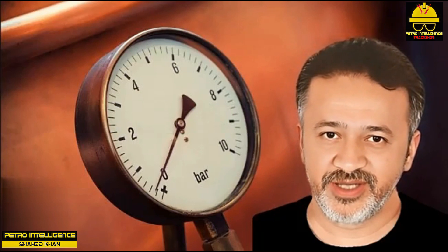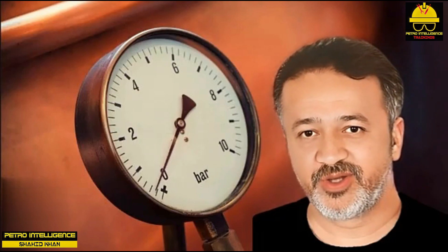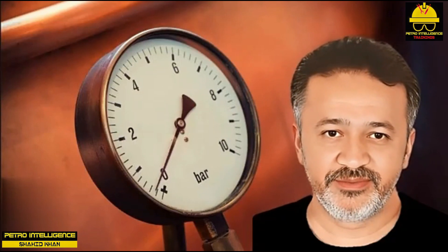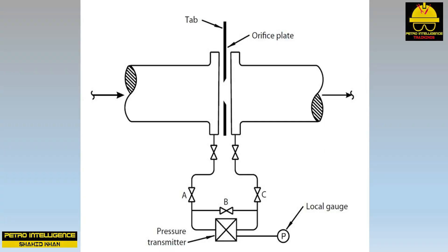Checking flows in the field: a competent engineer does not assume the flow indication shown on the control panel is correct. Referring to the picture, place an easy-to-read pressure gauge in the position shown — a digital gauge works well. By opening valves A and B with C closed, you read the upstream pressure. By opening valve C with A and B closed, you read the pressure downstream of the orifice plate. The difference between the two readings is ΔP — solve for V using the preceding equation.